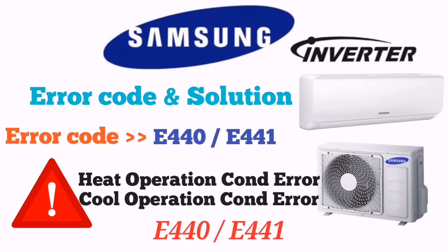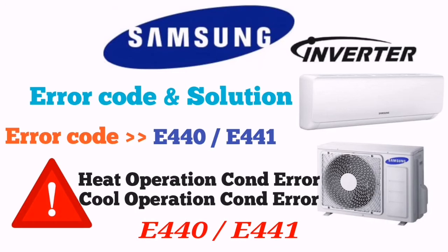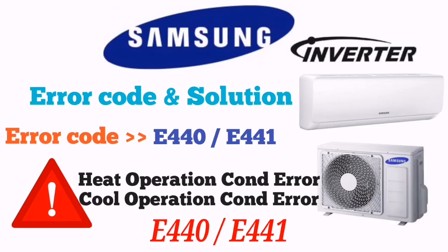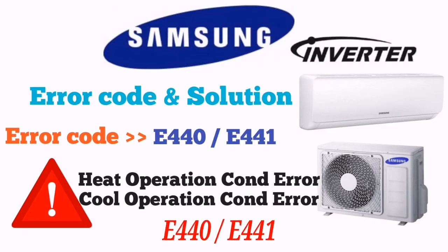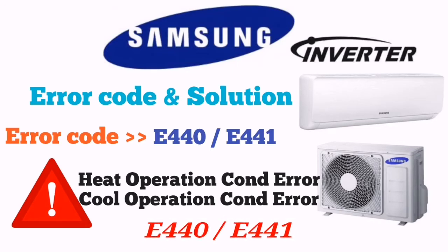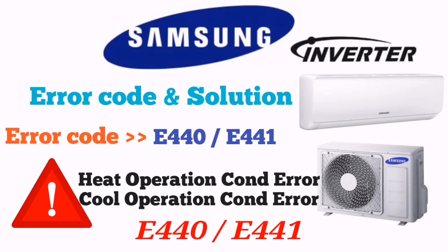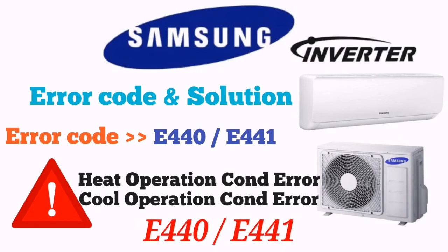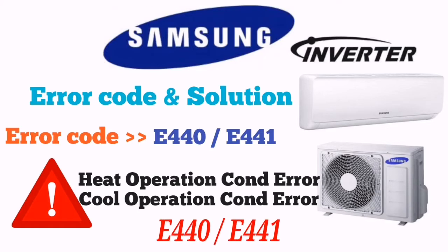When you see error E440 or E441 in your outdoor unit, or your LED 1 is on, LED 2 is blinking and LED 3 is off, it means it's an operation condition section error. It means an operating condition error for heating or an operating condition error for cooling. In some cases, in cold climate areas or hot climate areas, we get this error. To solve this error, you have to check your outdoor condenser coil and outdoor area.